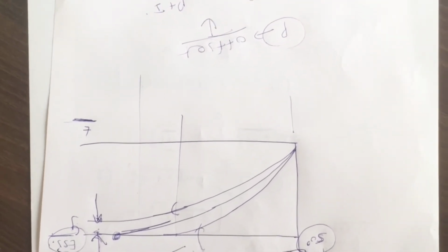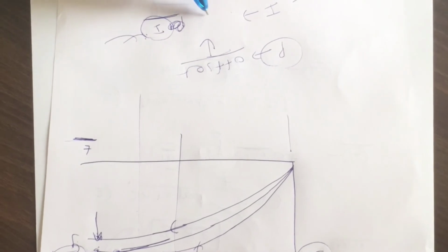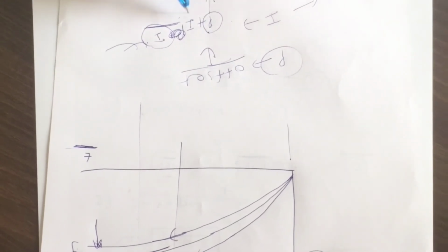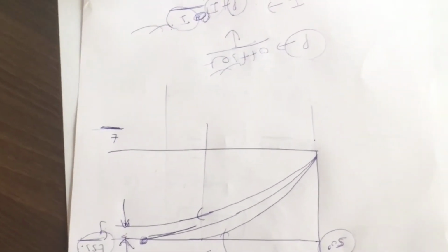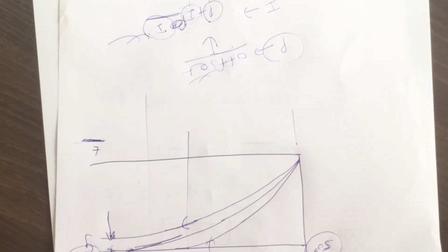Hope you understood the concept of the proportional mode and its limitation. The limitation of proportional mode is an offset error when the load changes. Integral mode, when used alone, is very slow and requires a lot of time, and that's why we combine P and I together. Due to the P, the system becomes fast. Due to the I, the offset error present due to the proportional mode is eliminated. Hope you understood this PI mode. The procedure for the PID and PD is similar to this one.